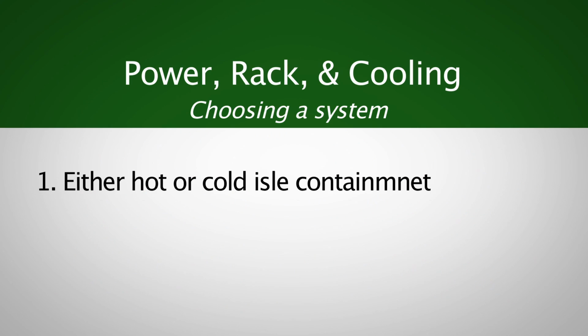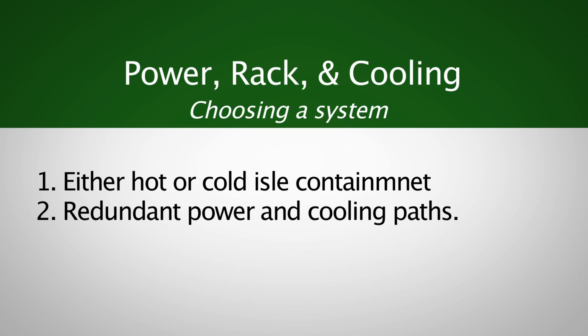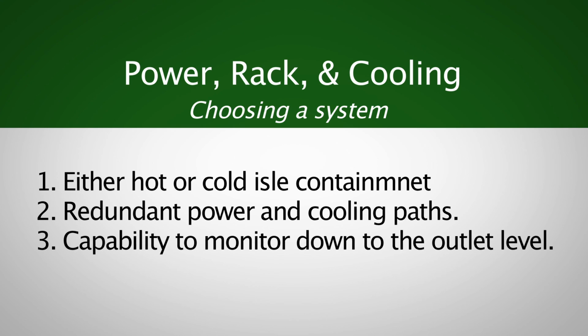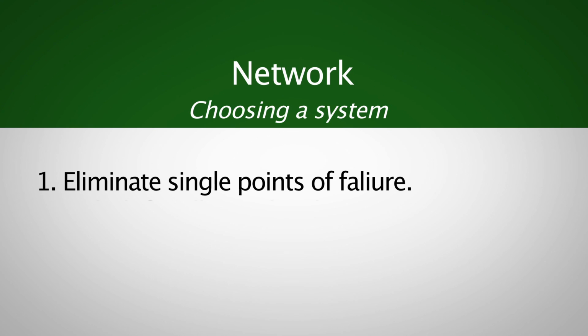In terms of our power, rack, and cooling, through our research, we decided we needed to choose a system that employed either hot or cold aisle containment, redundant power and cooling paths, and had the capability to monitor down to the outlet level. On the network, we needed to eliminate single points of failure in terms of hardware and infrastructure.